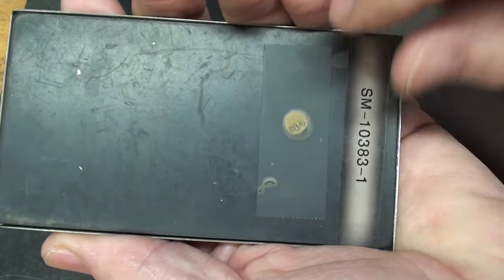The bottom sample here also is really scratchy, isn't it? So we should get this reading. Let me take a couple readings on here and I'm going to find from practicing here, I've already found out that the readings are going to be fairly close to this but not exactly. That may be due again to things out of calibration or the diamond has been damaged, banged around from being in a shop.